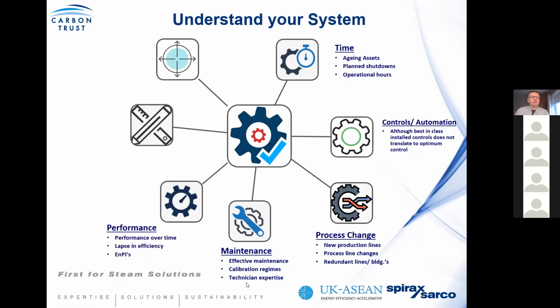Again, performance: what we see is performance over time. You get a drop in efficiency, or the energy performance indicator becomes worse over time because of the impacts of the other points we just mentioned. We also spoke about design, and time and time again, we find that poor design is a significant contributor to poor efficiency. And lastly, we look at site expansion. How has your site grown over the years? Have you added additional steam systems? But most importantly, the choice of how you interconnect to the existing steam distribution system. Remember, we spoke about pipe size, pipe dimensions, and steam carrying capacity. People sometimes think, oh, let's just interconnect to the steam header here and the steam system will work effectively, without doing the due analysis to see whether it is the correct connection point and the impact it may have in the boiler house, for example.